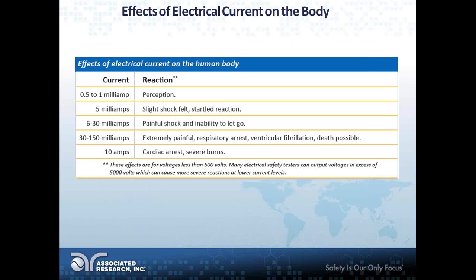When we move up to the next tier is really when we're getting into trouble, in the 6 to about 30 milliamp range, and again that varies for men and women—the threshold is actually slightly lower for women than for men. That's when you have a painful shock and possibly an inability to let go, with muscle contraction that means you actually cannot let go of the circuit. That's bad news, because the longer you're exposed, the worse the damage, and the better the chance you'll go into cardiac arrest.